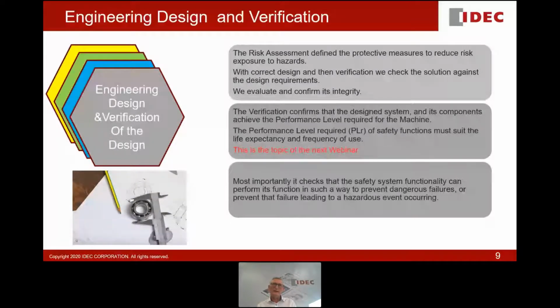And most importantly, the verification process checks that the safety functionality can be performed in such a way to prevent dangerous failures. Nobody wants to open a door and find the machine still running. And of course, if we can't actually protect against those dangerous failures for any reason, then we may have to ensure that the person isn't exposed to hazard as a result of that. Nothing is fail-safe, but we can do a great deal through this cyclical process to ensure that we have identified everything that can go wrong and how we can protect against it.